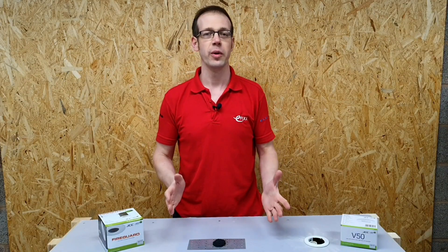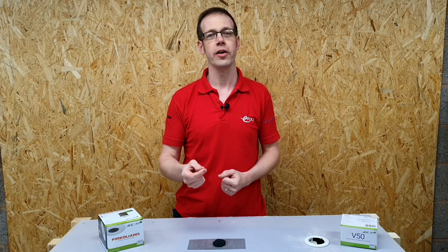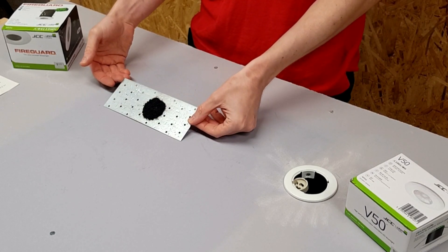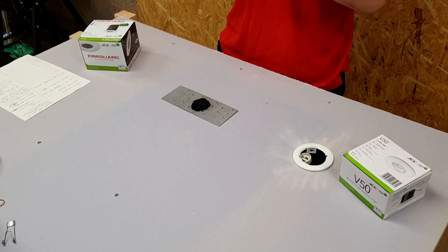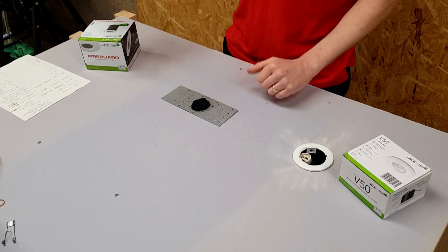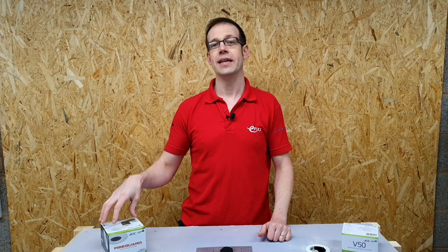So in this video we've seen some of the areas where we might find 30, 60, and 90 minute fire rated ceilings, how their construction differs, the key points of a fire rated light fitting, and what happens when a fire breaks out underneath one. A couple of further key points to consider: first, you have to make sure your light fitting has been approved for use in the specific type of fire rated ceiling you're installing it into. If you're installing into a 90 minute fire rated ceiling, the product must be tested and approved for 90 minutes. Also, don't assume that just because it's got the biggest number on it, it's acceptable for lower rated ceilings — a 90 minute fitting going into a 30 minute ceiling doesn't automatically mean it would pass the tests for 30 minutes. It must say the specific time for the type of ceiling you're fitting it into.